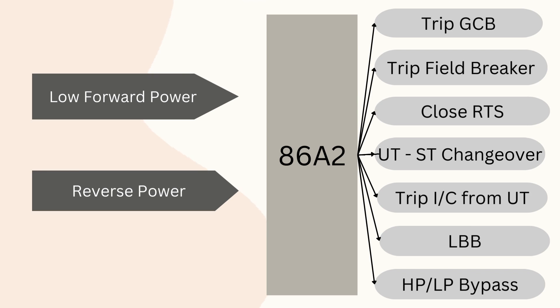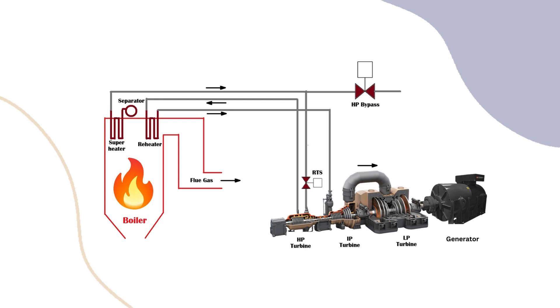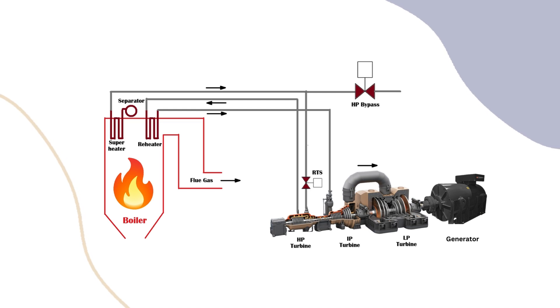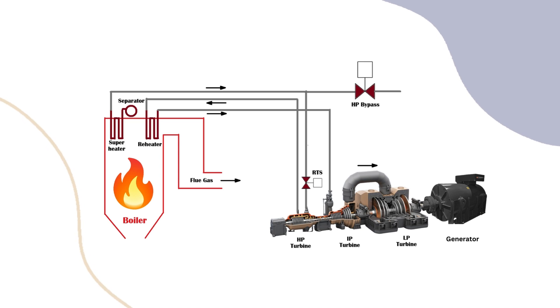Next, we will understand how Class B protection works. In this scheme, the trip command goes to the RTS to trip the turbine, the HP bypass to open, and the reheater protection system. Modern thermal power plants have three turbines: High Pressure (HP), Intermediate Pressure (IP), and Low Pressure (LP) turbines, sharing a common shaft with the generator rotor. High-pressure superheated steam from the boiler goes to the HP turbine, then to the reheater of the boiler to gather more energy, and finally passes through the IP and LP turbines.